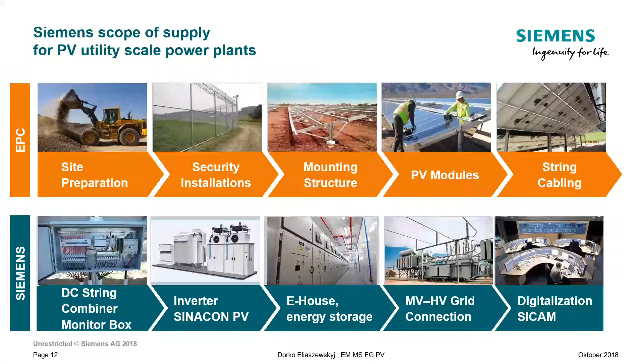Then it goes to the high voltage grid connection. Usually you have a 100 kV or 220 kV high voltage grid connection in large power plants, and of course digitalization by SICAM. This may be too technical, but from the bottom you see the modules, and then it goes up in voltage, first DC, then medium voltage, 33 kilovolt in this example, and up to high voltage, 115 kilovolt in this example. That's a standard single line diagram, very simplified, giving the technical people among you an impression of how we are thinking and designing.